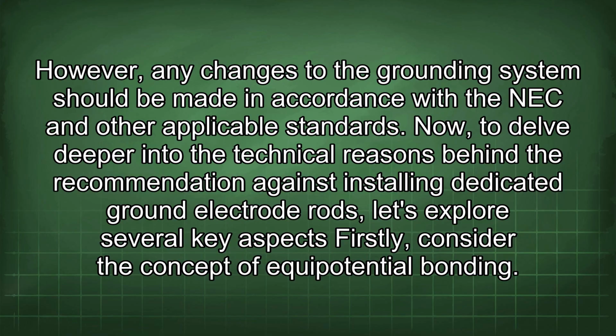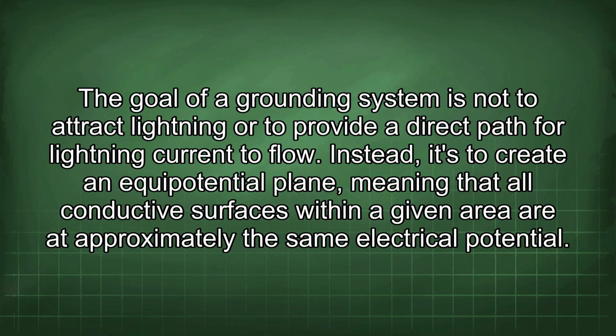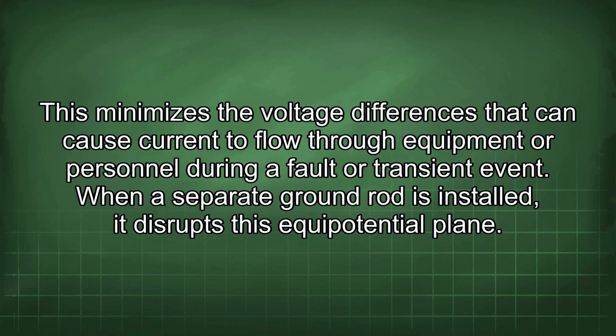Now, to delve deeper into the technical reasons behind the recommendation against installing dedicated ground electrode rods, let's explore several key aspects. Firstly, consider the concept of equipotential bonding. The goal of a grounding system is not to attract lightning or to provide a direct path for lightning current to flow. Instead, it's to create an equipotential plane, meaning that all conductive surfaces within a given area are at approximately the same electrical potential. This minimizes the voltage differences that can cause current to flow through equipment or personnel during a fault or transient event. When a separate ground rod is installed, it disrupts this equipotential plane.